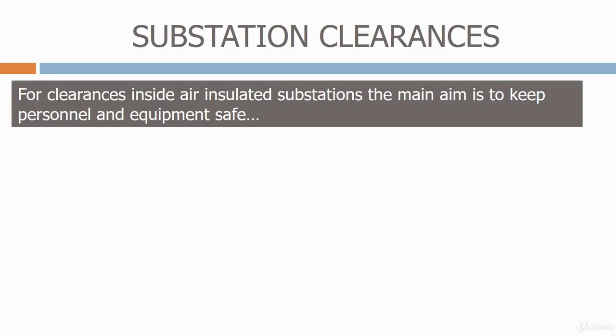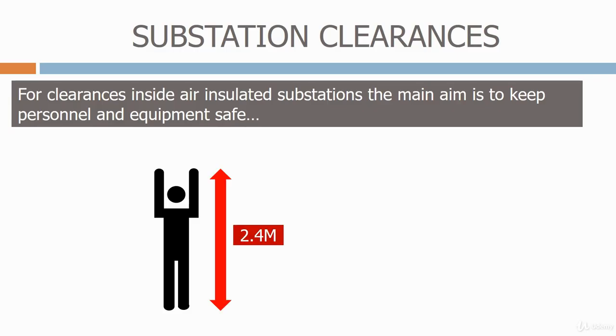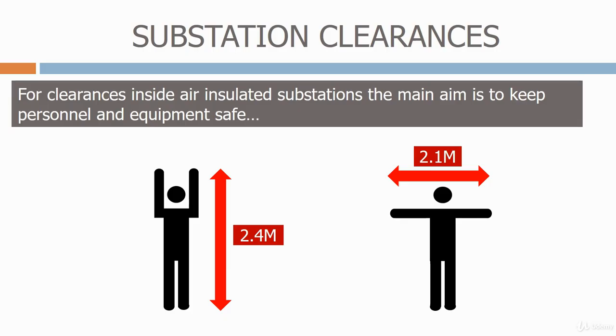For clearances inside air-insulated substations, the main aim is to keep personnel and equipment safe. To do this, we need to make some assumptions on the typical reach of the human body. For a person standing on the ground, we assume that the maximum height they can reach is 2.4 meters. When they stretch their arms out, we assume that the maximum distance from hand to hand is 2.1 meters. We then add the arcing distances from the previous table to these distances, and then add a suitable safety margin.